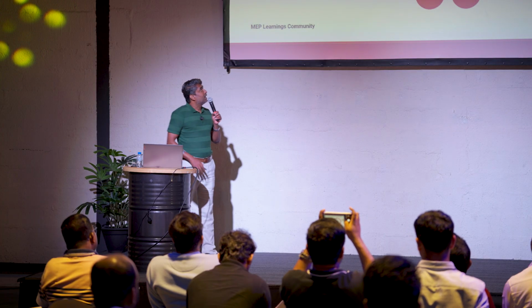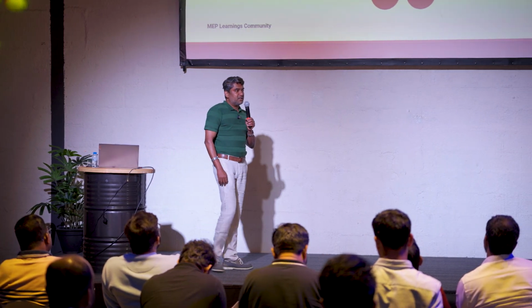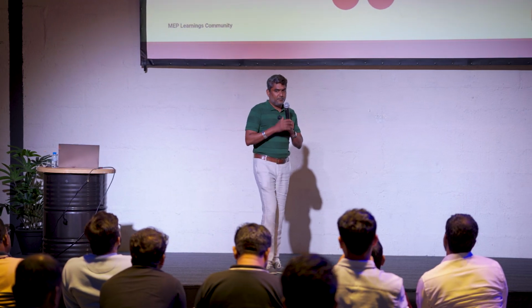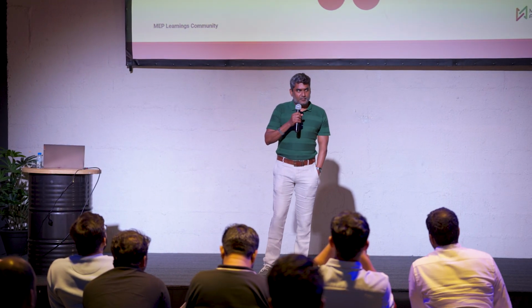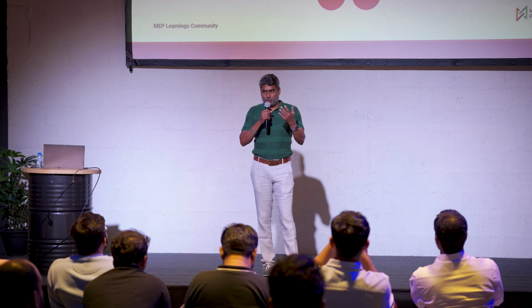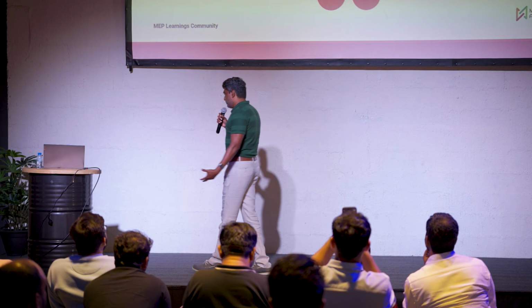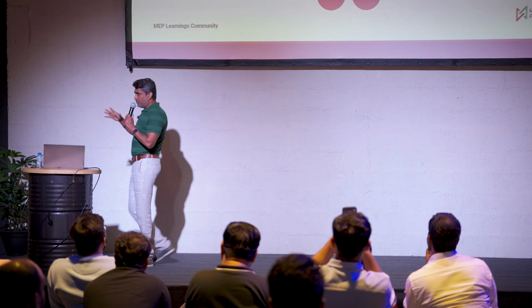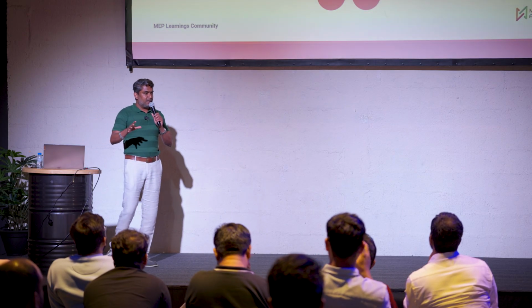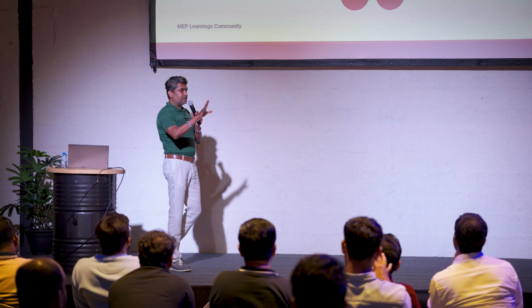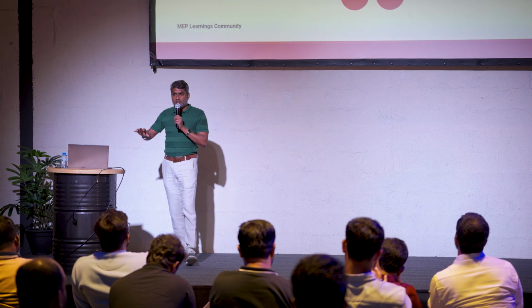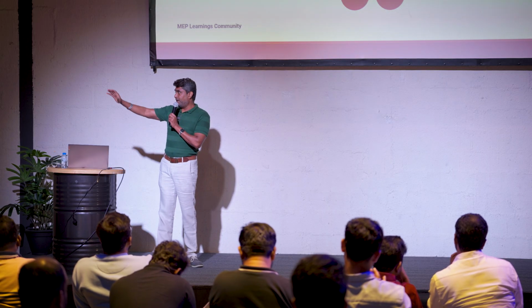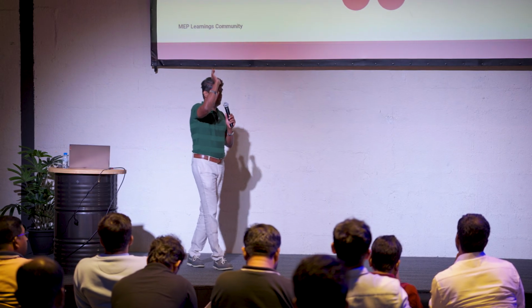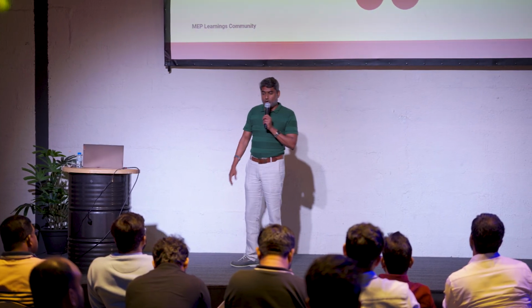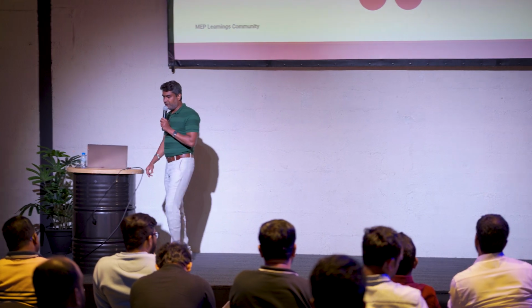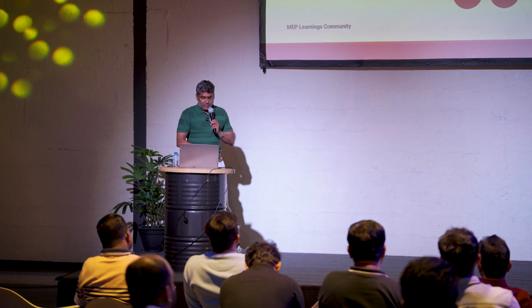The next item, emergency lighting. Why do you think the emergency lighting needs a signal? The emergency lighting system is intelligent enough to come online if normal power fails. But even then, to be double safe, the system sends a signal to the emergency lighting panel so that the non-maintained lights, along with the maintained lights which are the exit lights, all come on so the escape route is illuminated and people can safely evacuate.